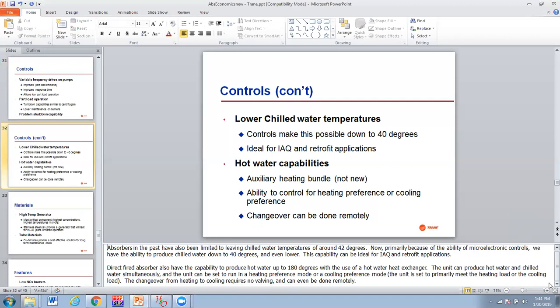Direct fire absorbers have the capability to produce hot water up to 180 degrees. We mentioned that previously. With the use of a heat exchanger, the unit can produce hot water and chilled water simultaneously and can be set to run in a heating preference mode or a cooling preference mode. So that's pretty nice. Changeover from heating to cooling preference modes requires no valving and can even be done remotely.